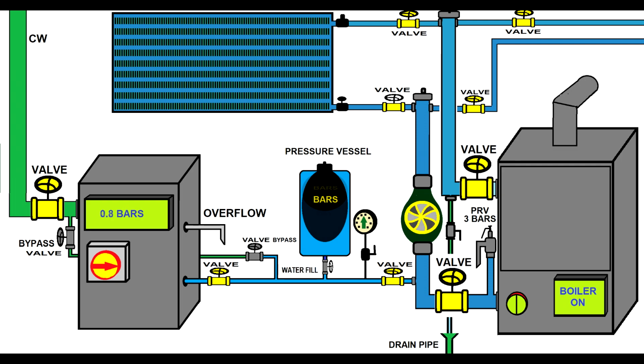While the temperature increases, the heating agent will also increase its volume. And if the volume cannot increase, then the pressure will rise. That's why we use pressure vessels, to allow the heating agent to expand. It is very important to choose the right pressure when we set up the pressurization unit, and it's also very important to pressurize the pressure vessel rubber bellow inside correctly. Otherwise, bad things can happen.